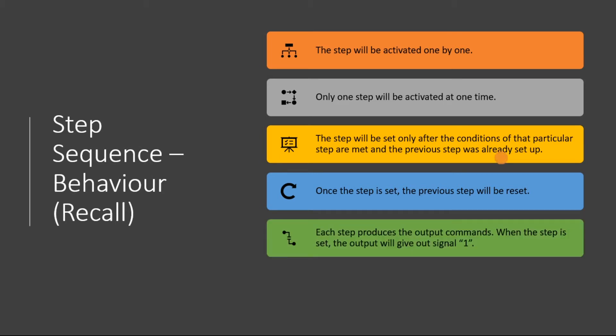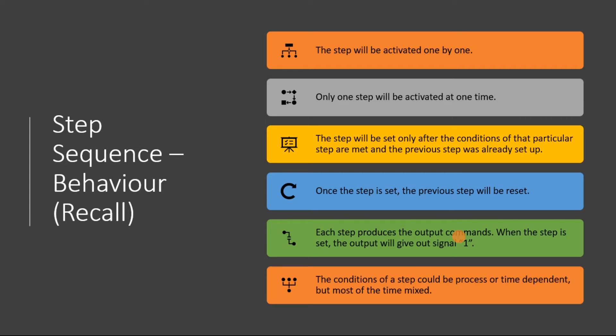Once a step is set, the previous step will be reset. Each step produces outputs, and when the step is set, the output will give out signal one. The output commands depend on the reset and set status of that output within that particular step. The conditions of a step could be process or time dependent — using a timer for example — or it can be both.